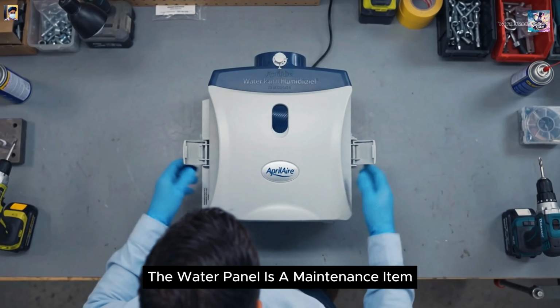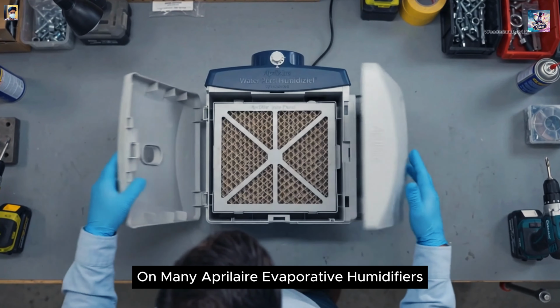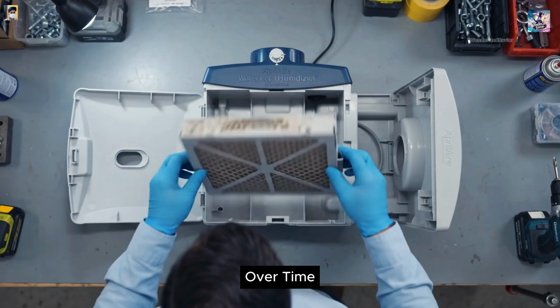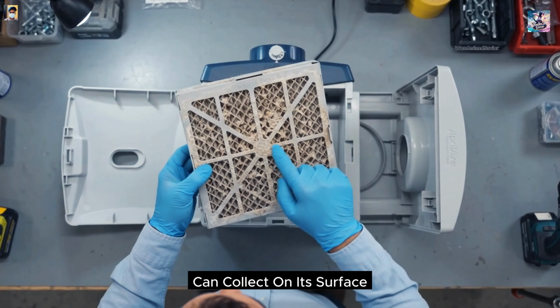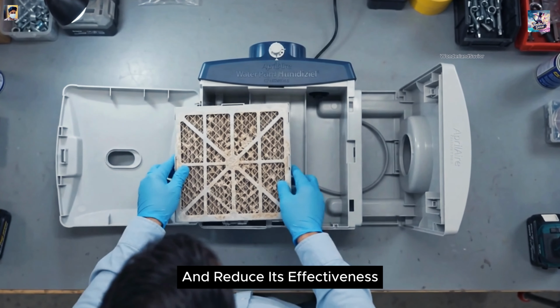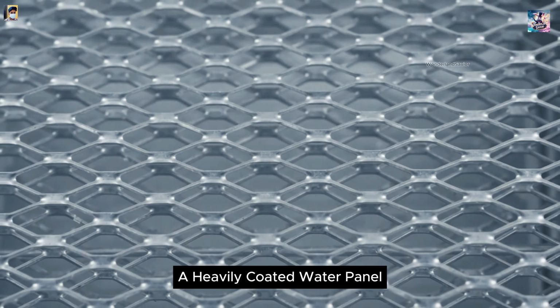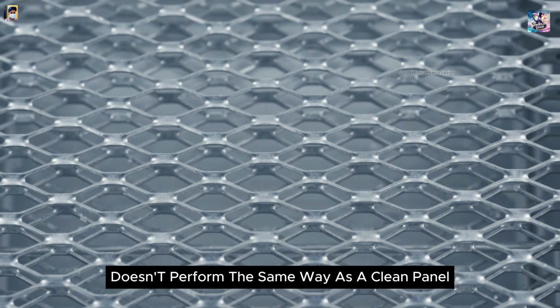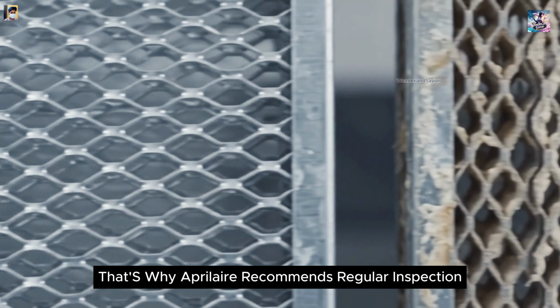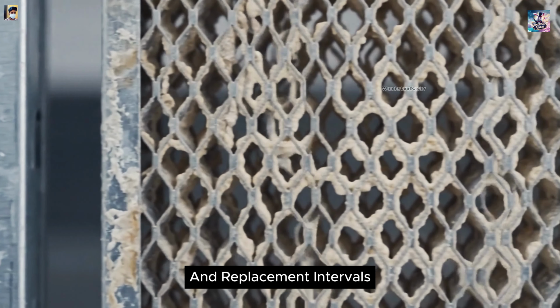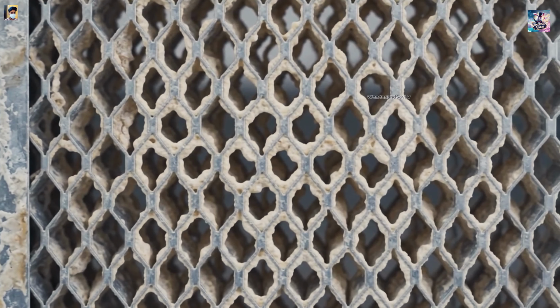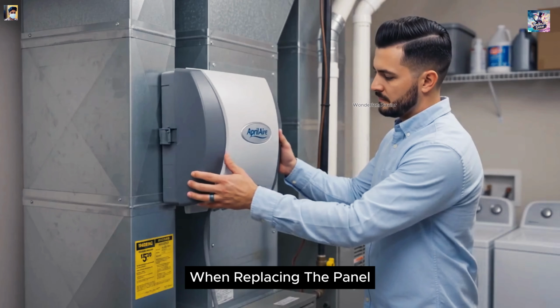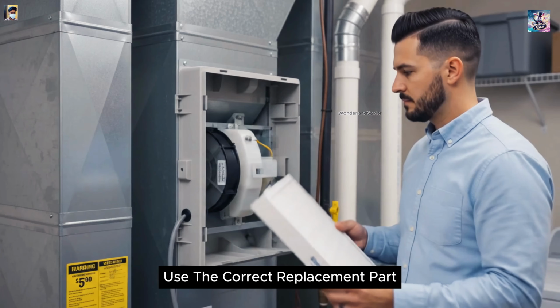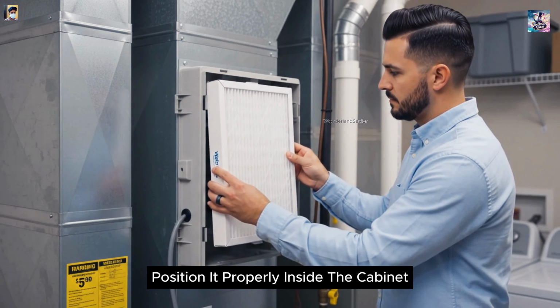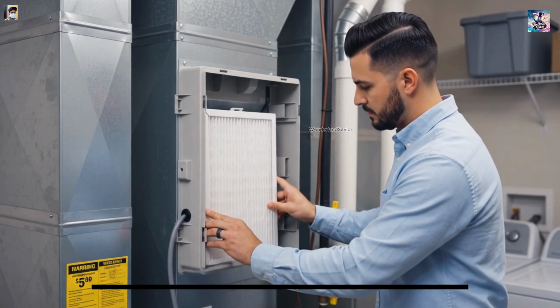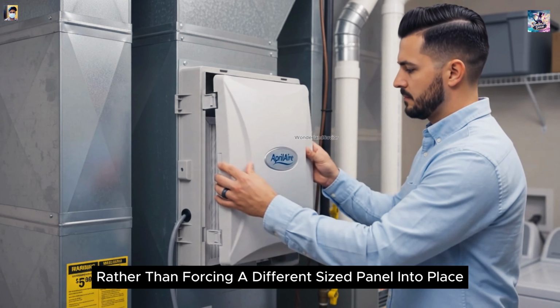The water panel is a maintenance item on many Aprilaire evaporative humidifiers. Over time, minerals from the water supply can collect on its surface and reduce its effectiveness. A heavily coated water panel doesn't perform the same way as a clean panel. That's why Aprilaire recommends regular inspection and replacement intervals appropriate for the specific model and installation. When replacing the panel, use the correct replacement part for your Aprilaire model. Position it properly inside the cabinet rather than forcing a different sized panel into place.